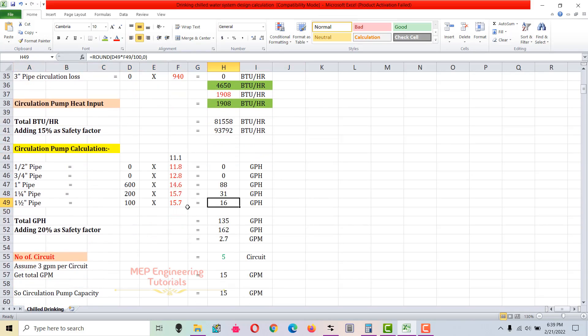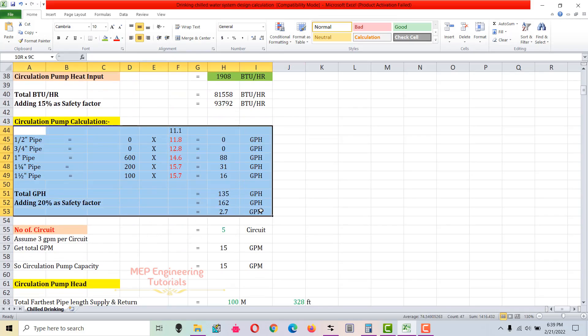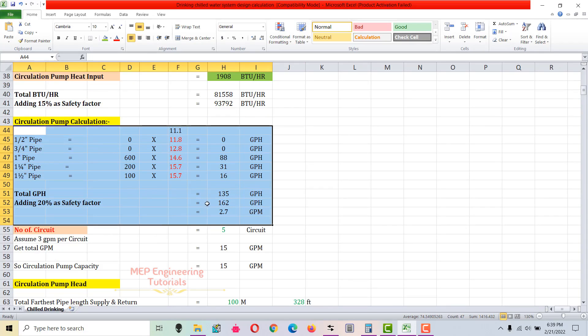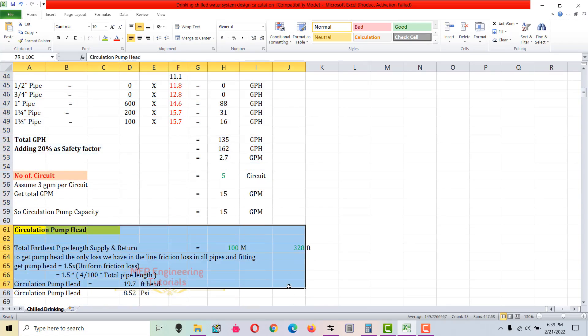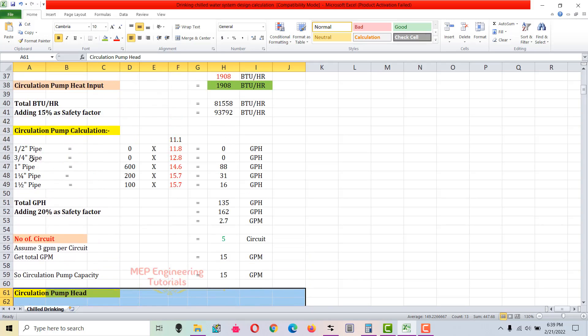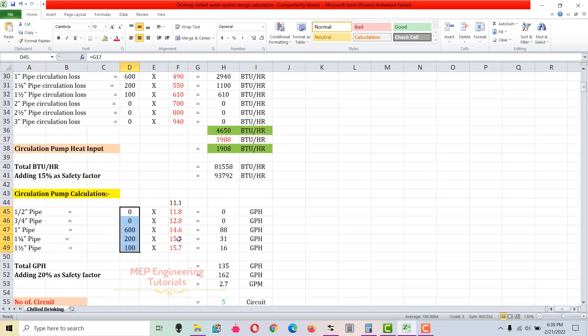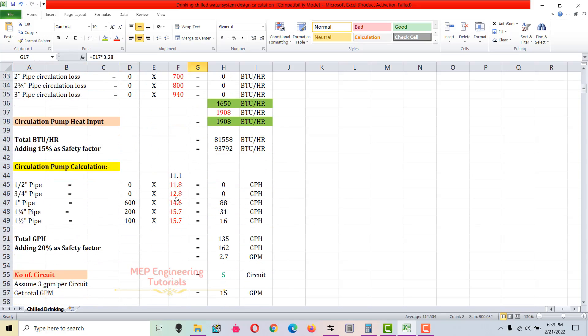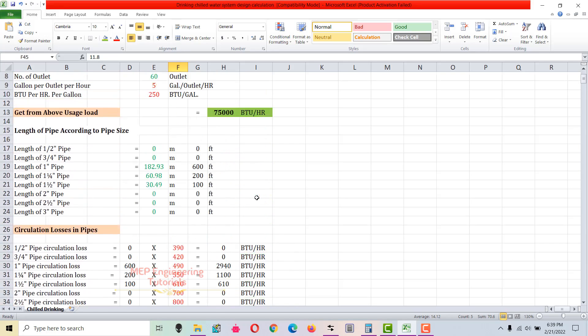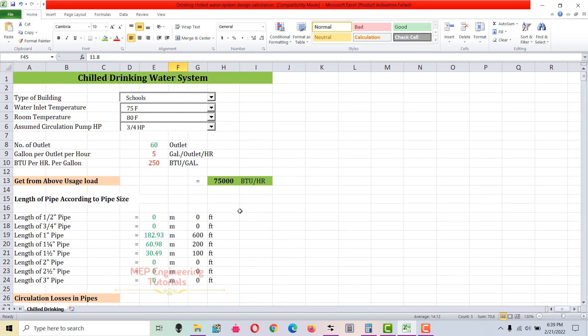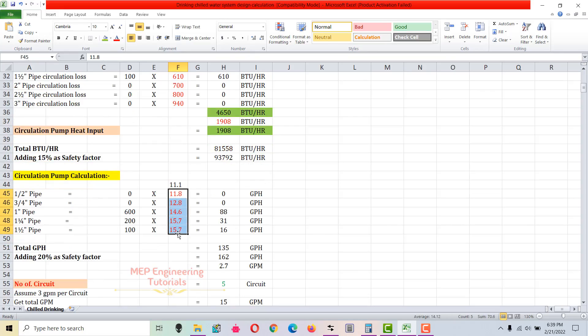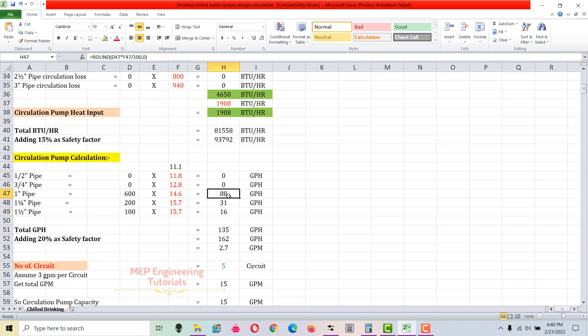Load calculation is done. Now we proceed to the circulation pump calculation, where we calculate the circulation pump capacity in GPM and the circulation pump head. I've entered all the pipes and lengths used in this project — the same lengths computed above. The red values are in gallons per hour per 100 feet of pipe. For the 1-inch pipe: multiply 600 by 14.6 and divide by 100 to get 88 gallons per hour.